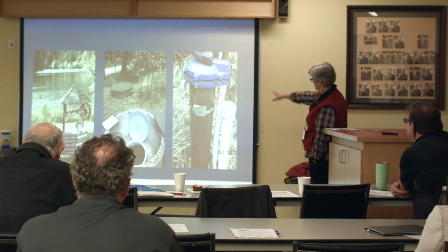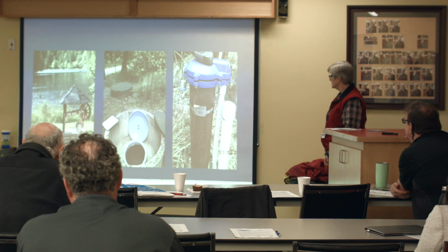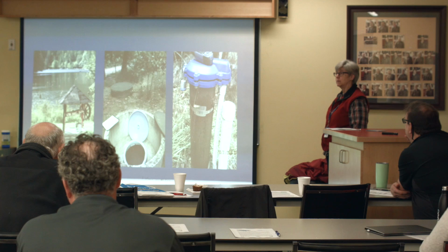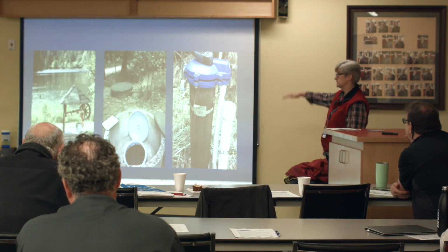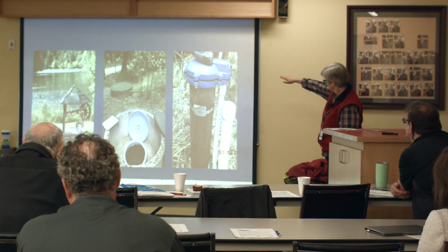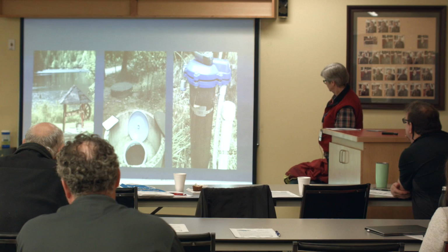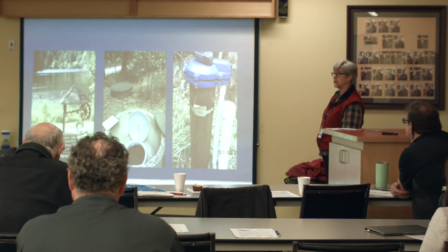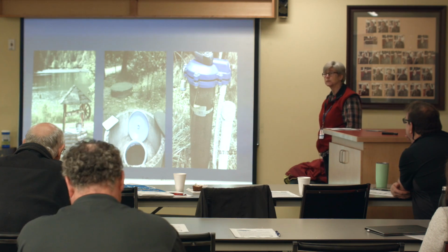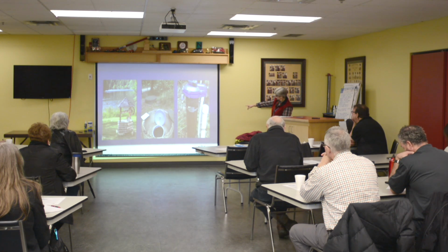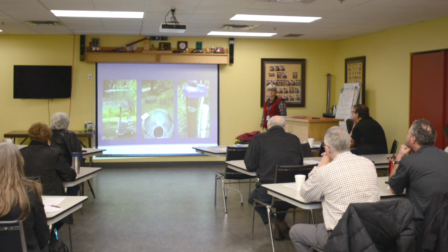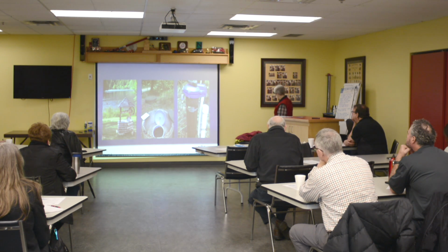And we have a nice drilled well that appears to meet all the requirements under the groundwater protection regulation. It sticks up above the ground. It's got a proper cap on it. It's got a well tag on it, so it has been registered with the ministry. And it looks like it also might have a monitoring well right beside it, checking depths of the water in it.